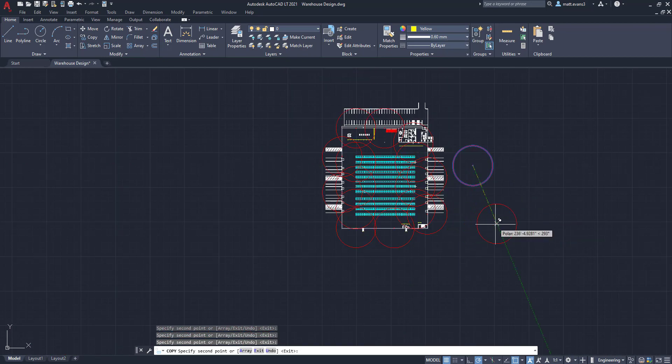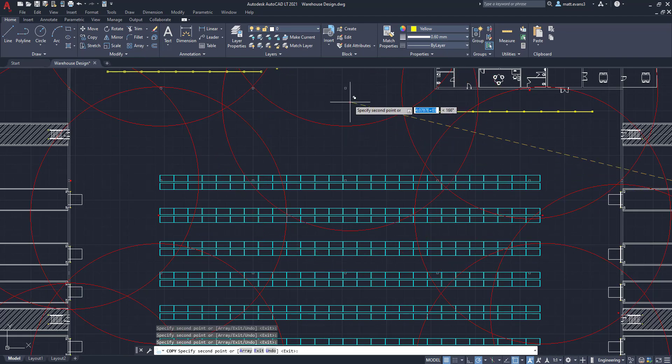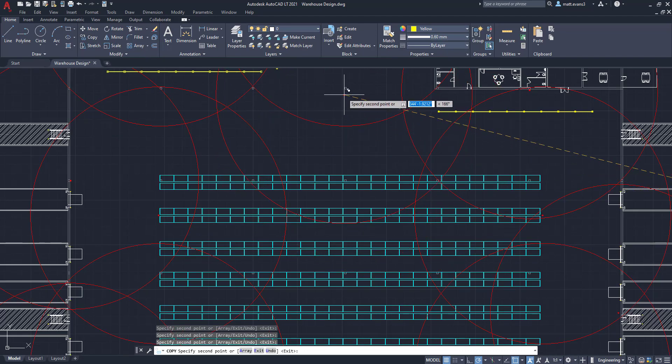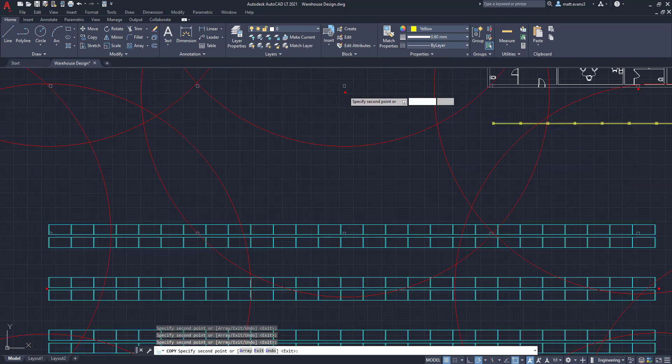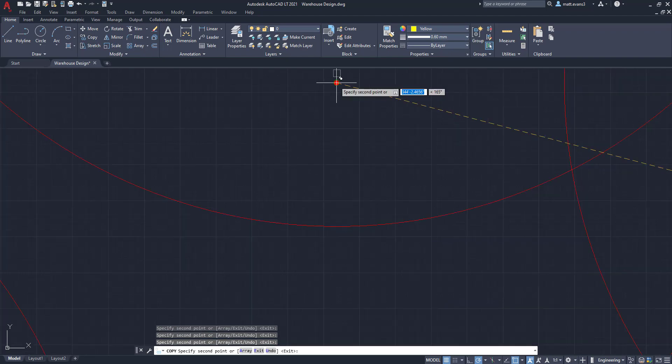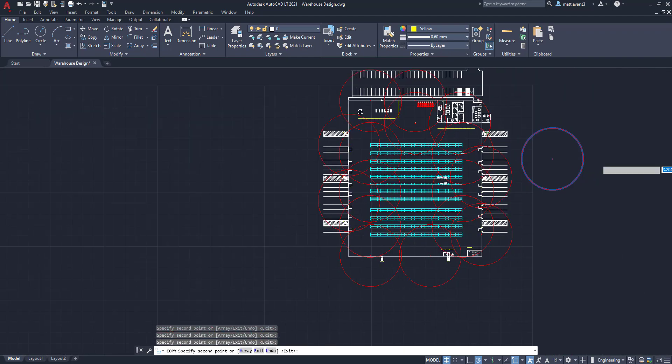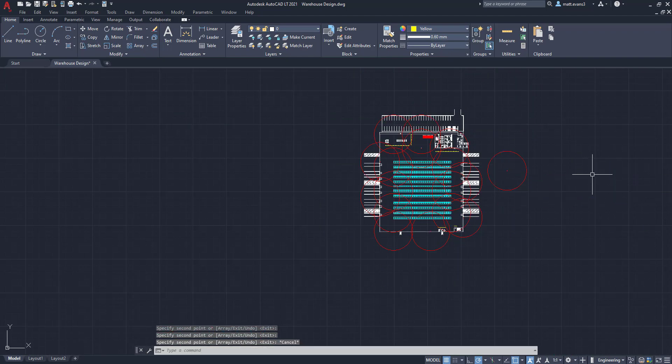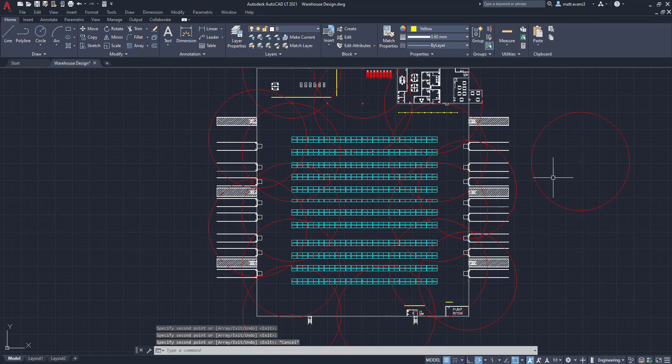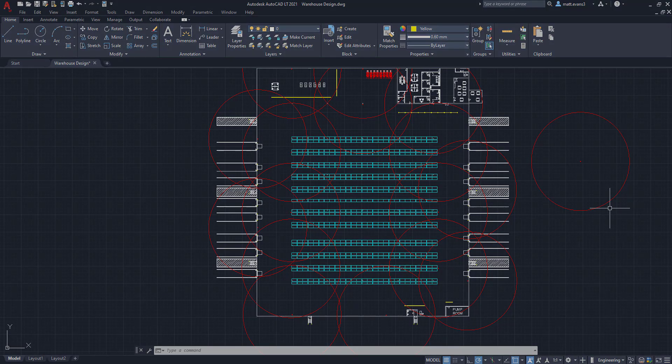And as you can see, your area in the rack is more covered now. We are also going to add one right up here against this pole just to cover this area right here, which was not covered previously. So now the only area that isn't covered by fire extinguishers is going to be this tiny little center area. And another thing to point out too, forklifts also contain fire extinguishers, typically. Lift trucks contain fire extinguishers. So if there's a fire in the aisle, there will also be a forklift with a fire extinguisher that can either be there at that aisle or drive down the aisle to extinguish it.